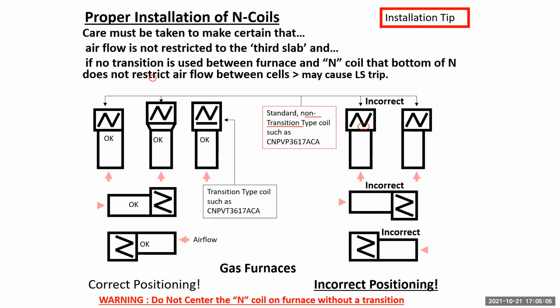I mean, don't just have an N coil sitting there on top of your furnace and say, "Oh, I tripped my right side, I'm gonna throw this higher limit in there and move on." You're gonna be back to have another limit trip problem. Need to have risers in there. Problem with that right side limit, if you look at these N coils, where your V is on the right side, your middle slab comes down, catches your right side slab and goes back up in that V. That right side limit sits pretty much directly above that limit, if that coil is centered on there, and it will come up. Your air hits the bottom of that V and creates an air block basically, and comes right back down on top of your limit and trips you out. So it's a heat trap.